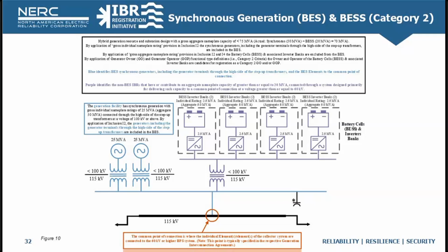you should come to the correct result. So here in this example, this depicts a hybrid generation resource and substation design consisting of synchronous generation and battery energy storage with an aggregate nameplate capacity of less than 75 MVA. The hybrid generation resource consists of 2 synchronous generators individually rated at 25 MVA and 8 inverters individually rated at 2.5 MVA, making up the battery energy storage component for an aggregate nameplate capacity of 70 MVA. Now, the common point of connection here, again identified by the orange circle, is at a voltage of 115 kV. So back to the resources.